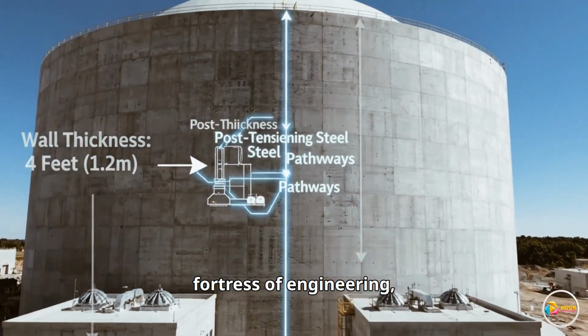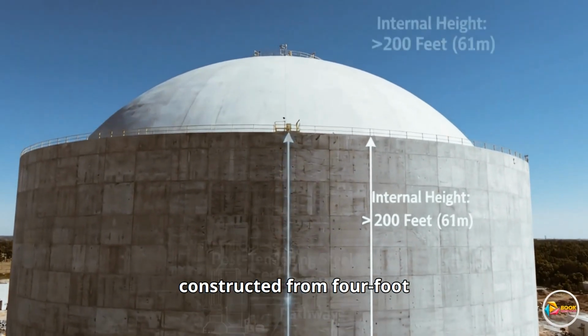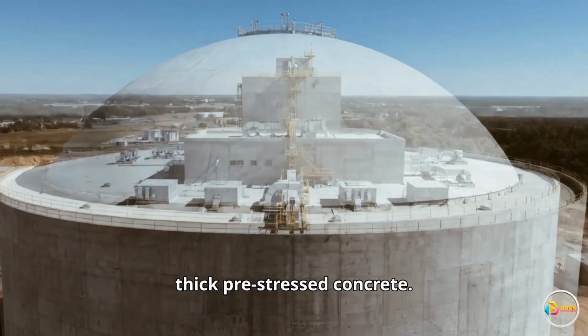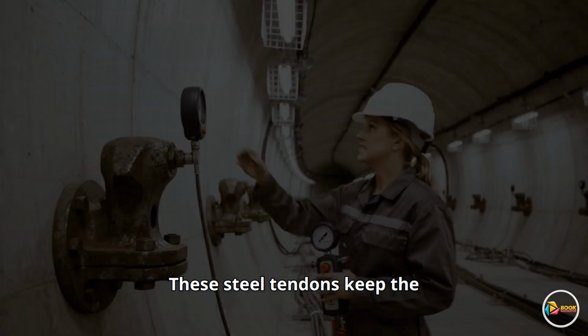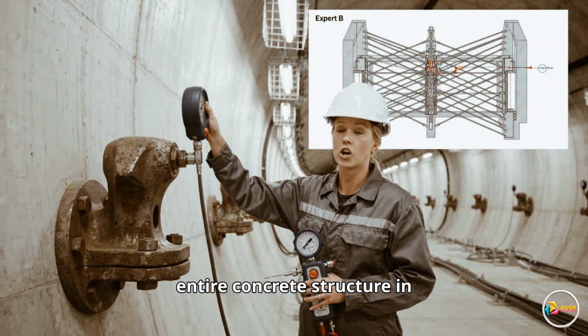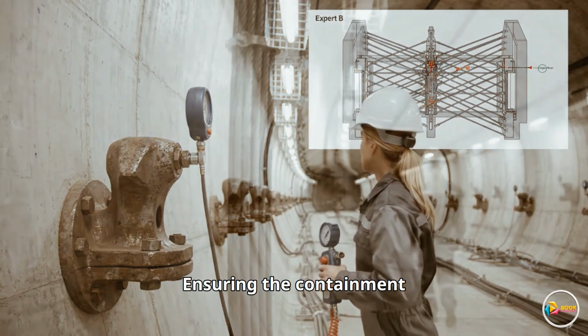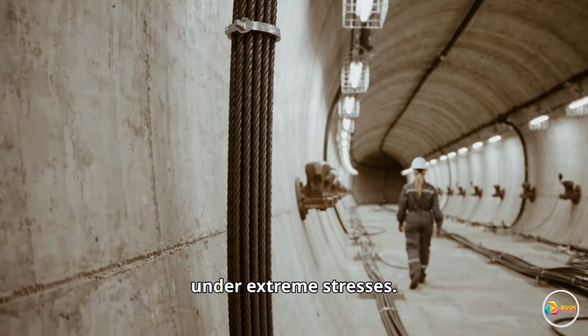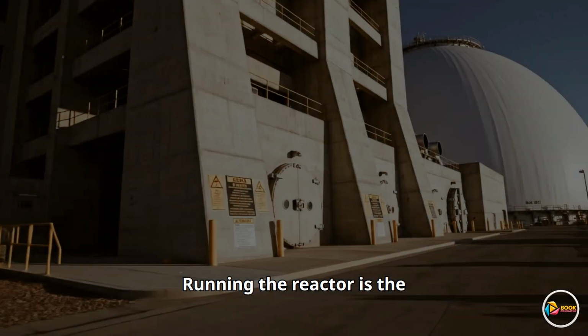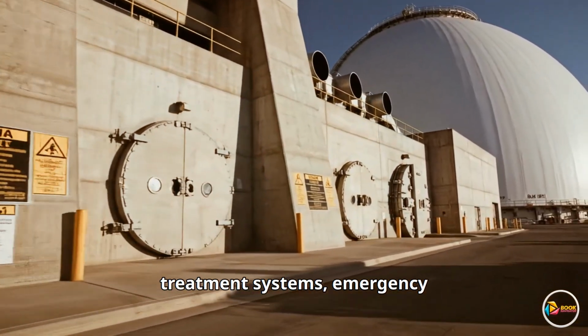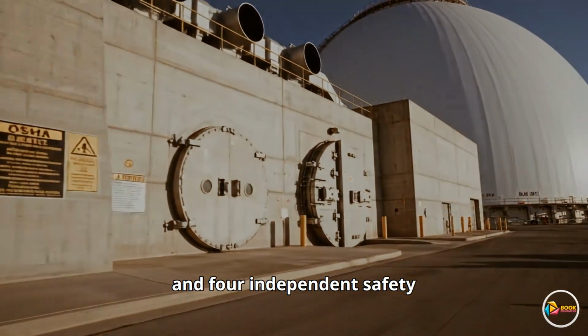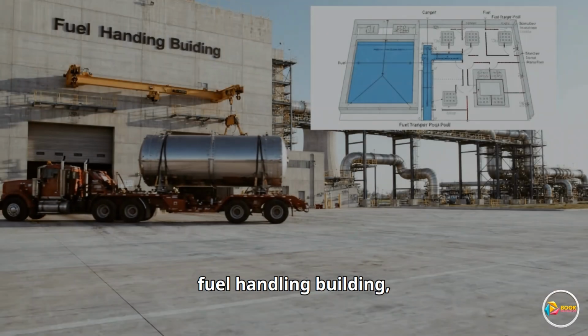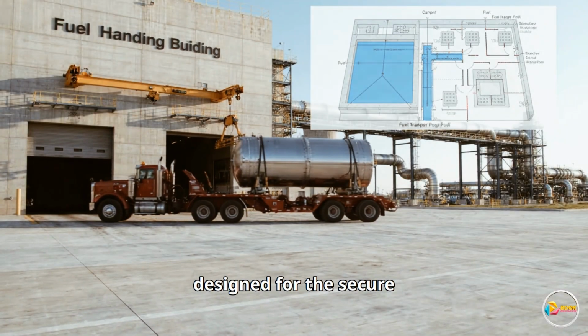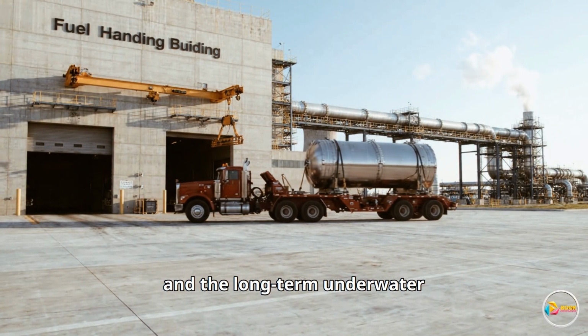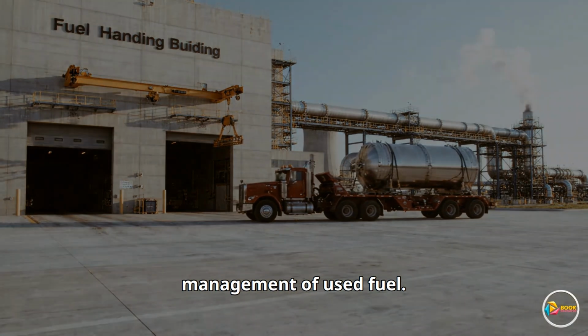The containment dome is a fortress of engineering, constructed from 4-foot-thick pre-stressed concrete. These steel tendons keep the entire concrete structure in permanent compression, ensuring the containment shell remains crack-free under extreme stresses. Surrounding the reactor is the auxiliary building, which houses the primary coolant treatment systems, emergency pumps, and 4 independent safety circuits. Adjacent to containment is the fuel handling building, designed for the secure delivery of fresh fuel assemblies and the long-term underwater management of used fuel.